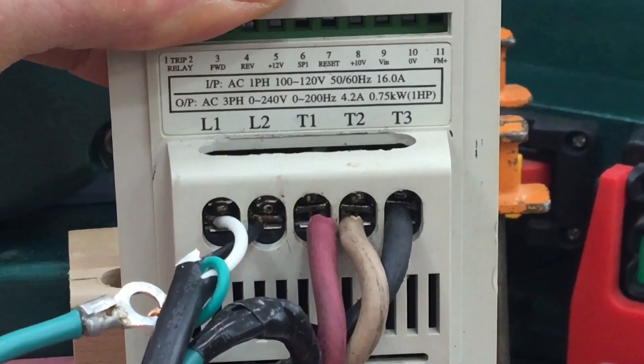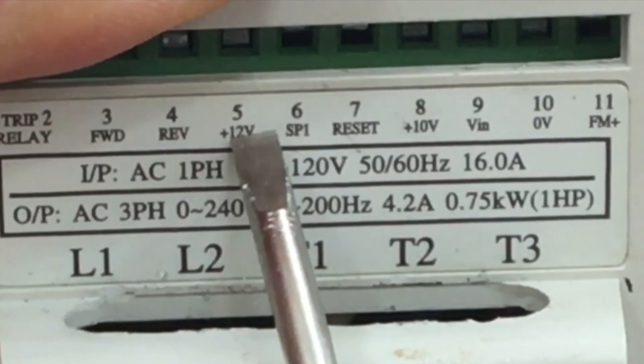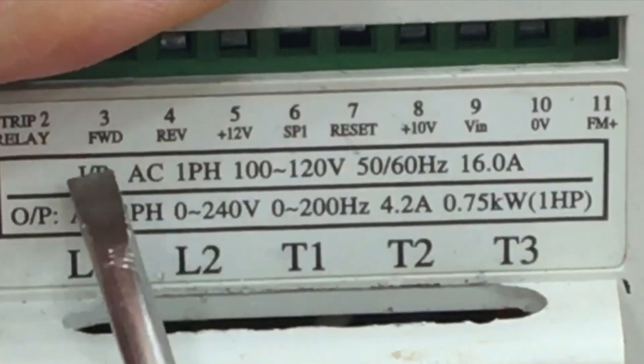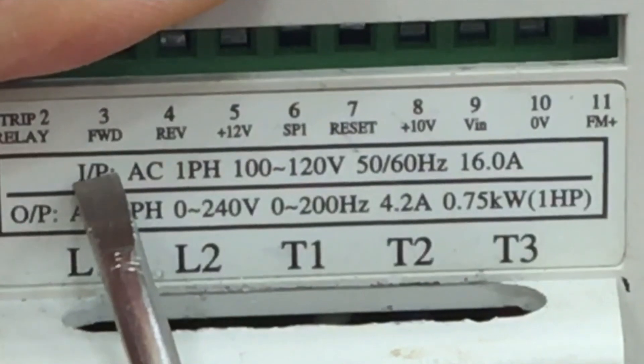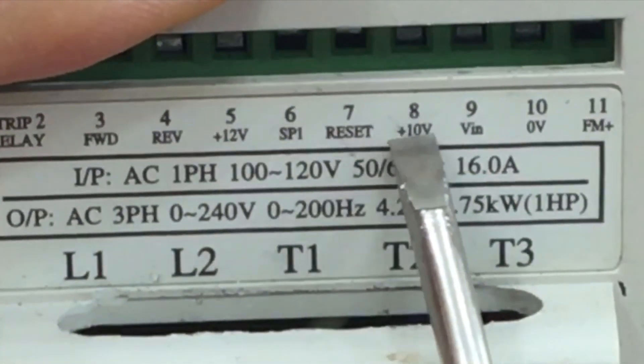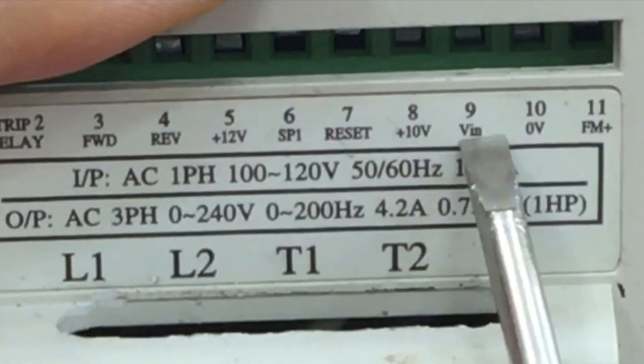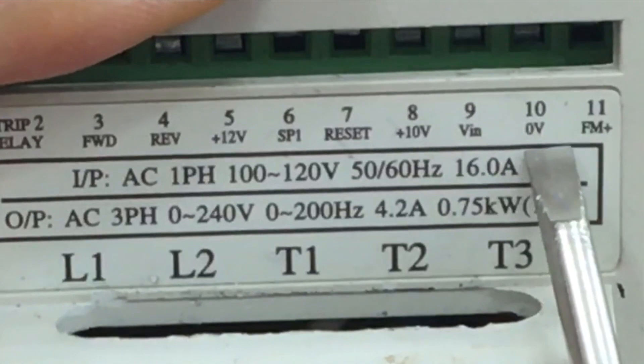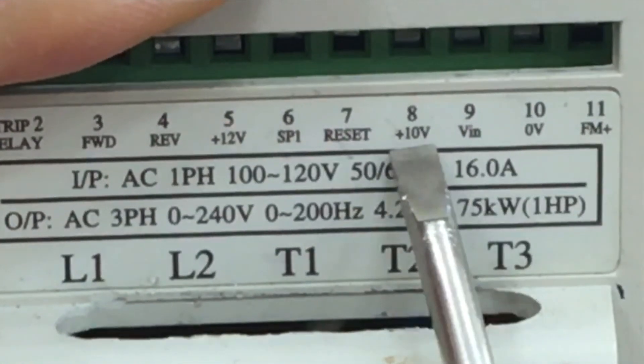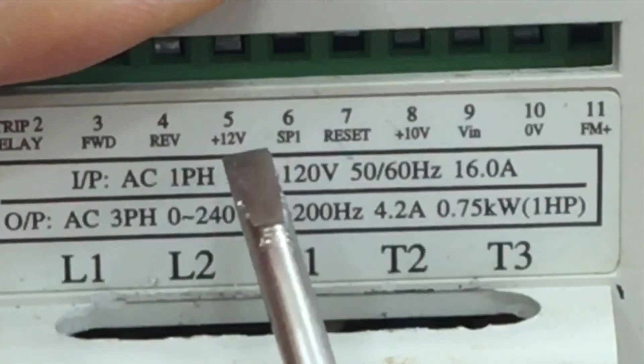So we have moved the control of the VFD from the keypad to this low voltage terminal. And there are 11 different terminal slots and we're only going to use six of them. Forward and reverse direction control is three, four, hooked to number five. And then 8910 is 10 volt, variable volt, and zero volt. That controls the frequency output of the VFD. These three will be attached to a potentiometer.